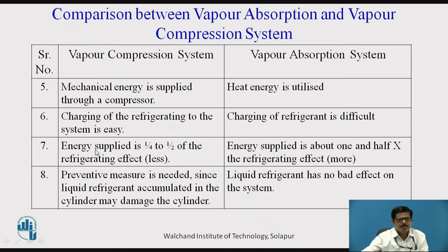In vapor compression system, the energy supplied is high-grade energy — electric power. This energy supplied is one-fourth to one-half of the refrigerating effect, so this energy supplied is much less. So COP is higher, performance is better. Whereas in case of vapor absorption system, we are supplying low-grade energy, that is heat. Energy supplied is heat energy in case of vapor absorption system — it is more than about one-and-a-half times the refrigerating effect. Therefore, the COP of this system is comparatively very less.